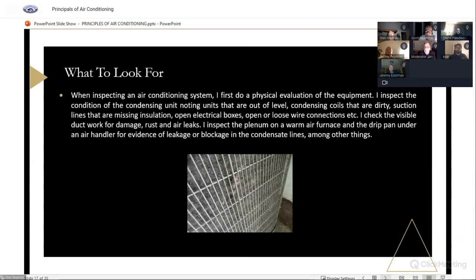You see a lot of loose wires, missing covers. I write all that up. I check the visible ductwork for damage, rust, air leaks. Plenum on a warm air furnace and the drip pan for leakage, blockage in the condensate lines. Anything that looks like it's out of the ordinary. And quite frankly, if I find any of that, I basically, at the end of the day, say this thing needs to be serviced by a professional to determine its exact condition, even though it may be running and it appears to cool the house.